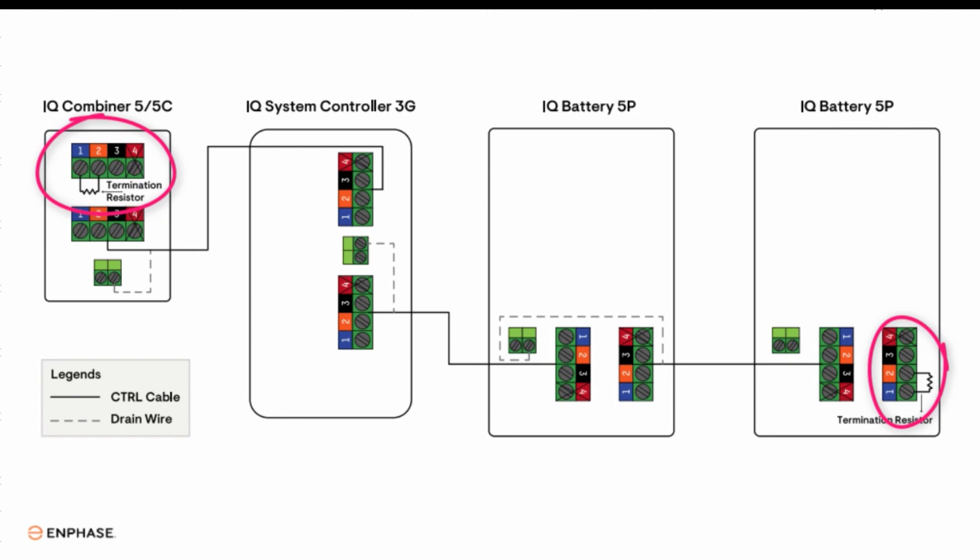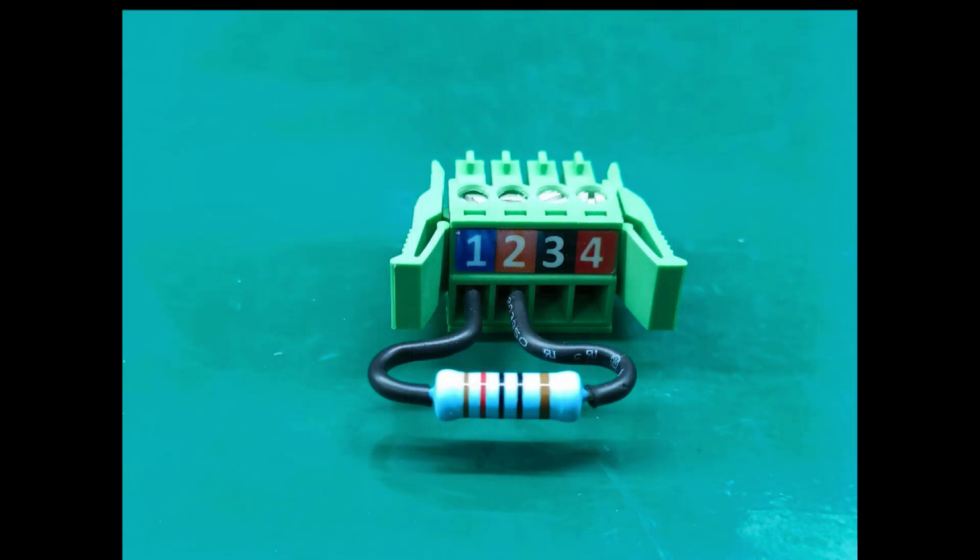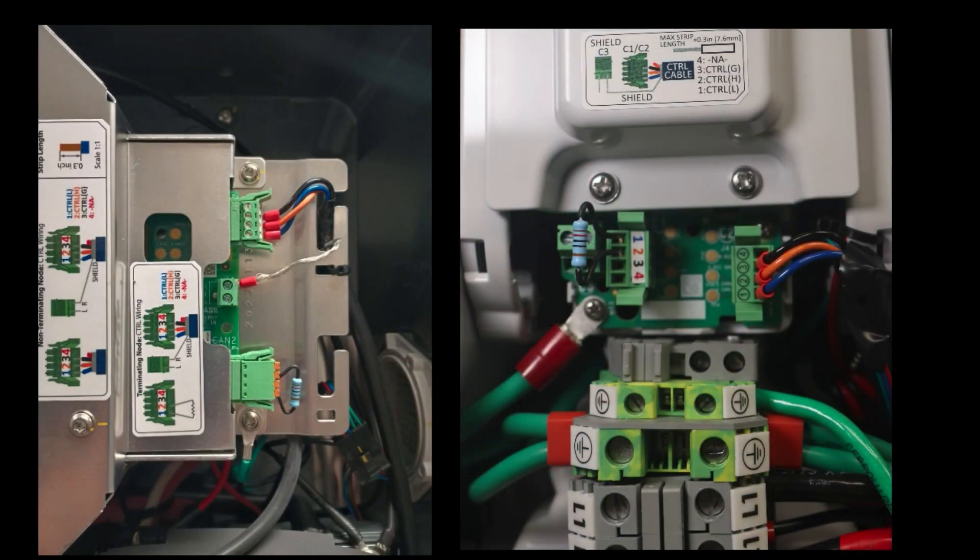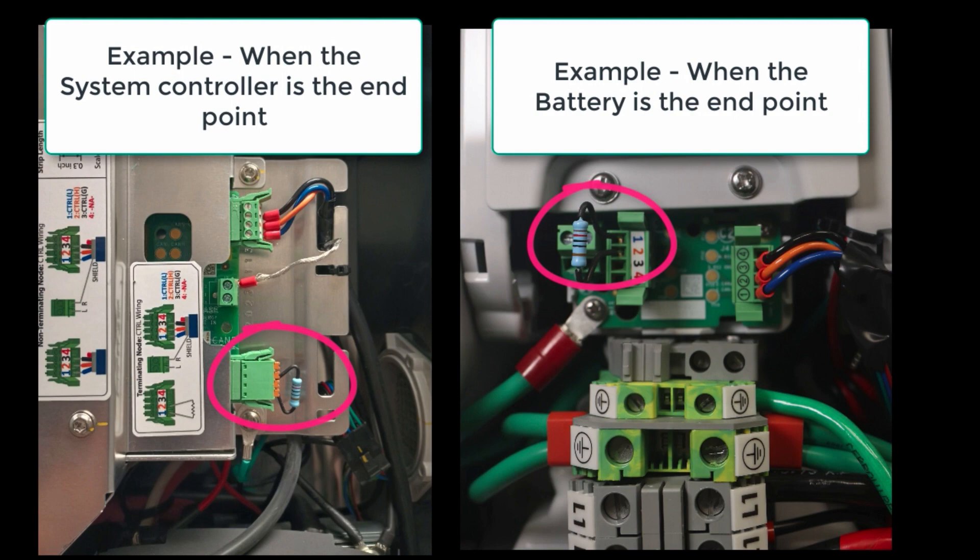Each endpoint device must have a termination resistor installed, wired between pin 1 and pin 2 of the wiring header. The header is then installed on the open control cable ports at the endpoint devices. Don't lose the termination resistor. It's included in the components but packaged separately.